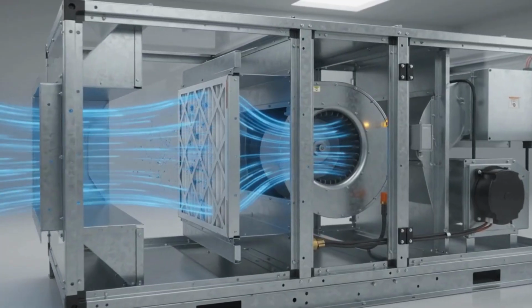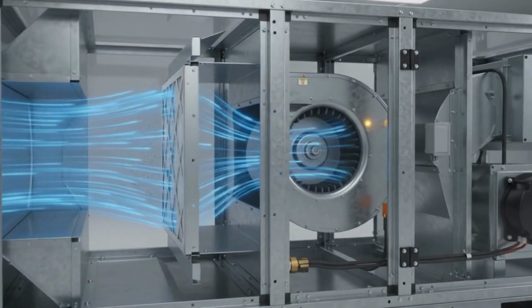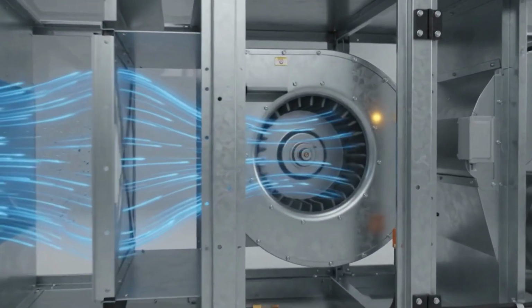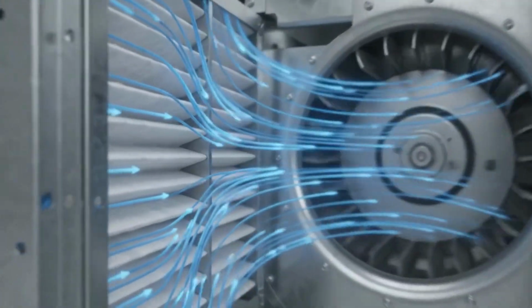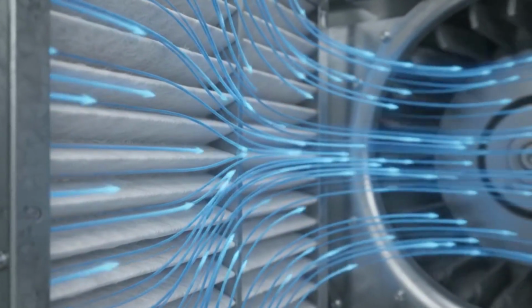Now, a lot of homes, especially if the returns are ducted, remember the duct goes directly back to the air handler. We put a filter in that grill. So now I'm filtering the air as it goes into the ductwork. Well, hey, Tom, that's a great idea. I don't want all this dirt and dust and everything going into my duct system, right? I want to filter it as close as I can to the room. Okay, you may have a concept there, but think about this.